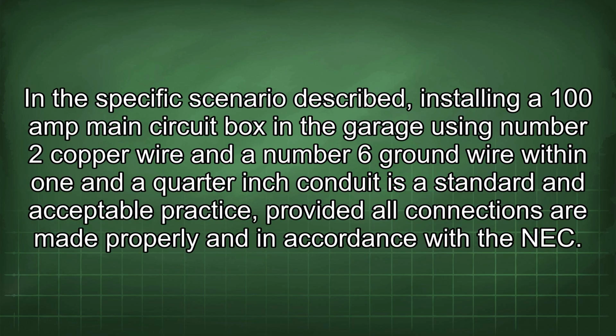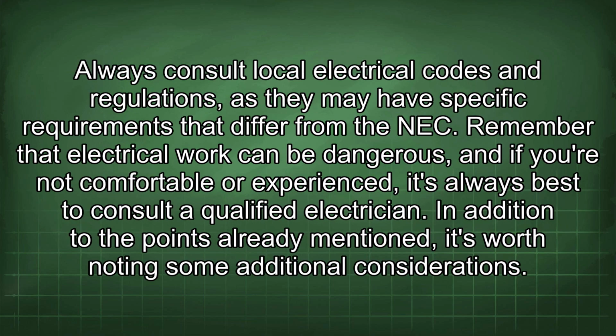In the specific scenario described, installing a 100 amp main circuit box in the garage using number 2 copper wire and the number 6 ground wire within 1¼ inch conduit is a standard and acceptable practice, provided all connections are made properly and in accordance with the NEC. Always consult local electrical codes and regulations, as they may have specific requirements that differ from the NEC.